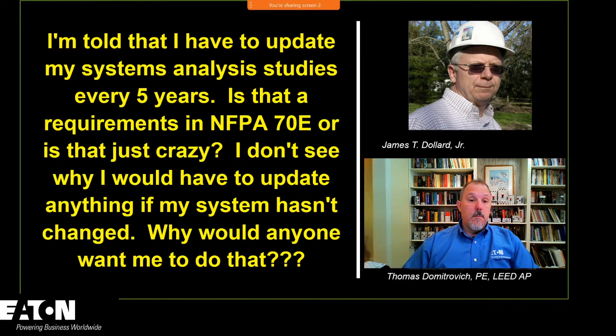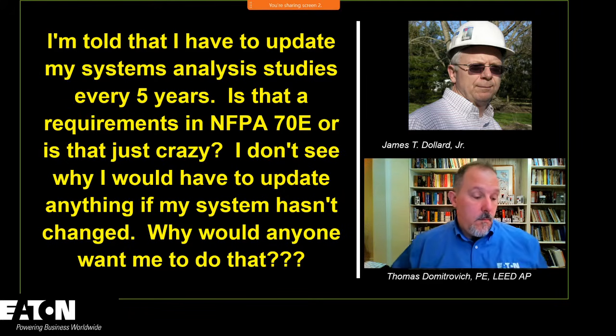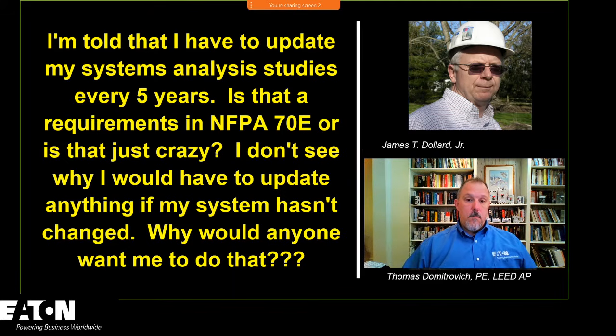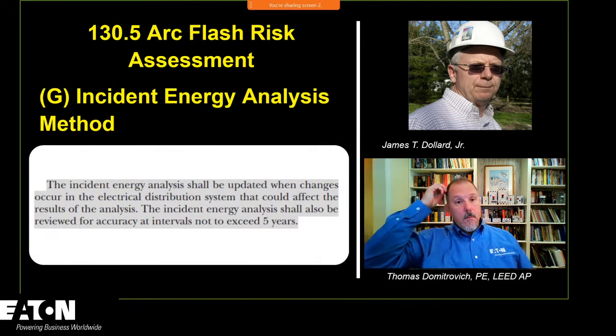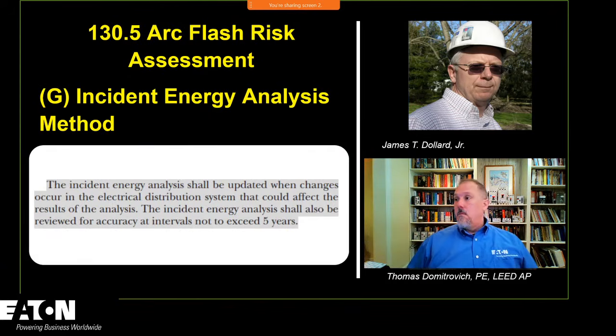That's exactly right. Maintenance is probably the one thing that's often overlooked, and it's critical. In the standard, the incident energy analysis shall be updated when changes occur in the distribution system that could affect the results of the analysis. If you don't maintain your equipment, then changes are occurring.